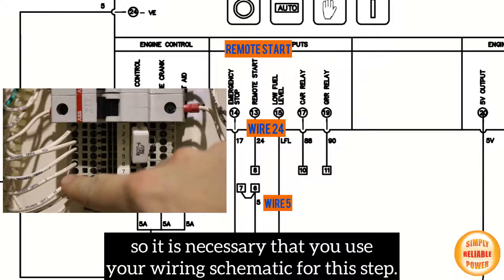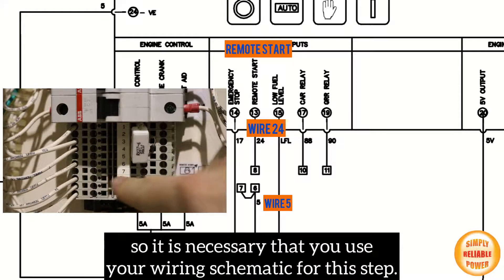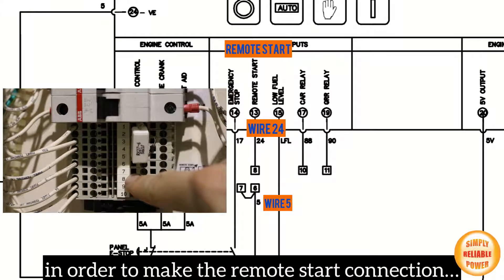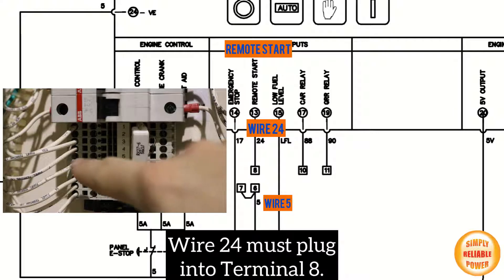It is necessary that you use your wiring schematic for this step. As we can see from this example, in order to make the remote start connection, wire 24 must plug into terminal 8.